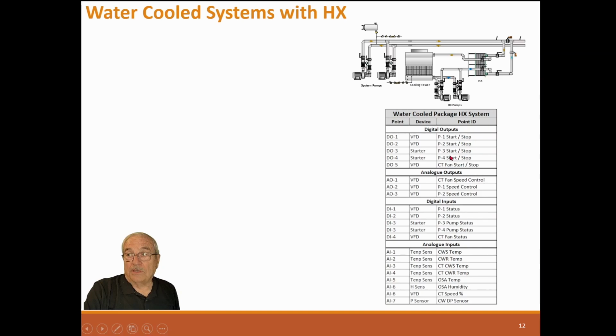So here's the point list. DO1 is this pump start-stop. DO2 is this pump start-stop. DO3 is this pump start-stop. DO4 is this pump start-stop. DO5 is the cooling tower fan start-stop. Analog outputs are the VFD cooling tower fan speed. And we made this one here. This is assuming that these pumps are variable speed. They don't have to be, but they can be. So if this has valves on the equipment out here and has that differential pressure sensor, then these can be variable speed, and I left that this way.